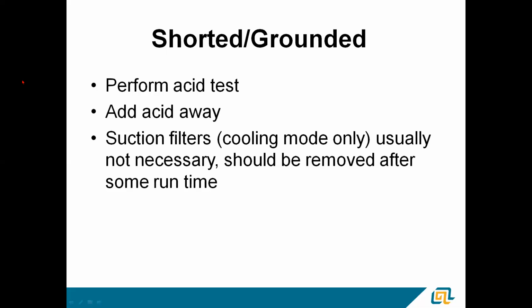It's a little harder to measure a temperature drop across a suction filter, but most suction filters are designed with a port on the inlet side of the filter, a gauge port you can connect your gauges to, and there's also one, of course, on the service valve of the unit, so you can see and monitor the pressure drop across that filter. If you get 3 pounds of pressure drop across that filter, it's time to get it out of there. It'll just lead to more troubles and heartaches.